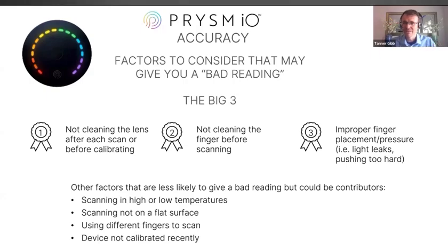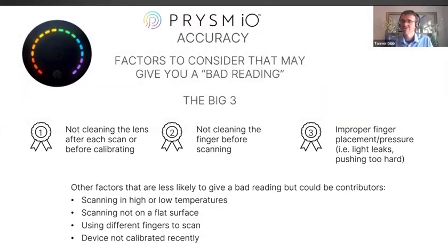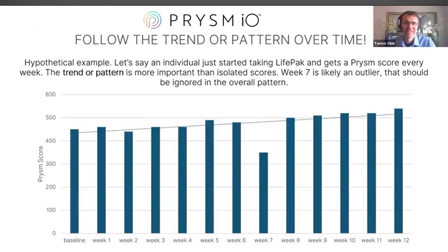But the big three, if you can just focus on those big three, make sure that you clean the lens before every scan and before calibrating, right? Clean your finger before each scan and make sure you have the proper finger placement and pressure. Those three things are going to be the biggest variables for giving you the most precise scan each and every time. Now, it's really important to consider this device and statistics when we talk about what criteria we want to focus on and what criteria we don't want to focus on.